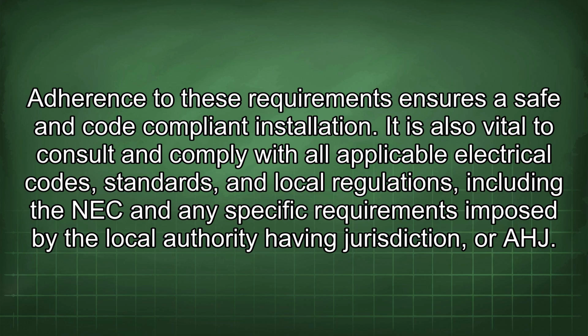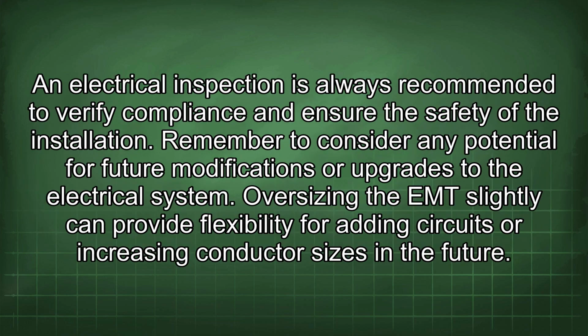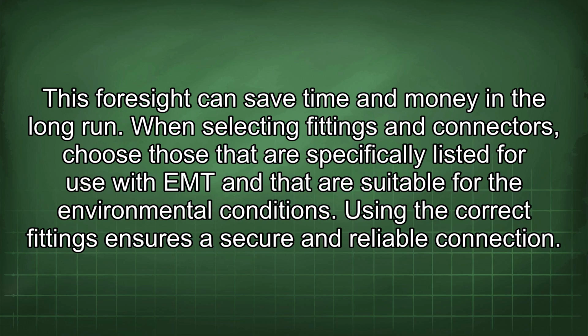It is also vital to consult and comply with all applicable electrical codes, standards, and local regulations, including the NEC and any specific requirements imposed by the local authority having jurisdiction, or AHJ. An electrical inspection is always recommended to verify compliance and ensure the safety of the installation. Remember to consider any potential for future modifications or upgrades to the electrical system. Oversizing the EMT slightly can provide flexibility for adding circuits or increasing conductor sizes in the future. This foresight can save time and money in the long run.